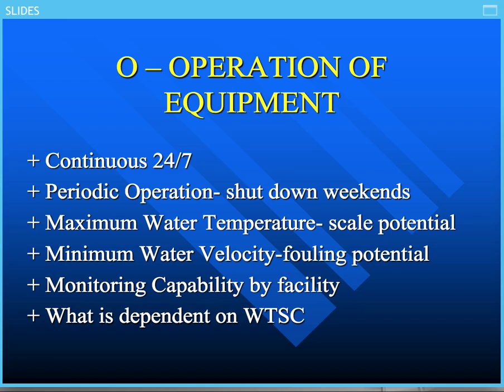Keep in mind, however, the operation of all of this equipment. If you're a refinery that has one heat exchanger operating at very high temperatures versus the rest of the heat exchangers in your plant, the question is, why let that heat exchanger scale up and have to descale it periodically, rather than spend the money to go to a higher scale inhibitor level to control that one small heat exchanger when the rest of them don't require that high level? Another aspect we look at is the minimum water velocity. We need to know if it is 1 foot per second or less. That is a big fouling tendency, like we showed earlier on the cooling tower fill. That can happen in the heat exchangers as well.